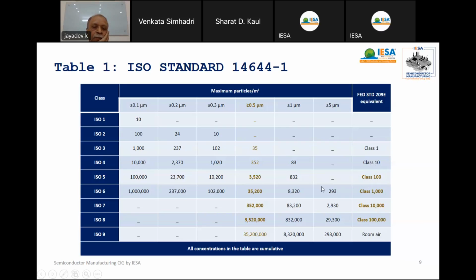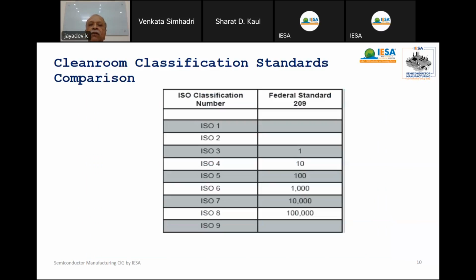air. Similarly, if you go for ISO 6, it's about 35,200 particles of 0.5 micron in 1 cubic meter of air in the room, which is equivalent to class 1,000 particles in 1 cubic feet of air. This is in general a standard ISO. Most of us will follow these standards. So for the benefit of those who are normally confused between ISO and Federal, I am giving a chart here, easy to understand.